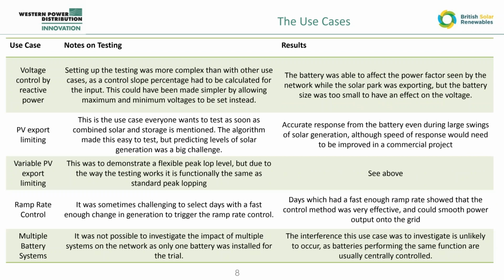And the final 5, voltage control by reactive power. So another way to control voltage is by adjusting the power factor between leading and lagging, and therefore the voltage can be controlled like that. High voltage is a problem in many areas due to the increased amount of distributed generation and sometimes the overnight underutilized assets. So this was also expected to help.